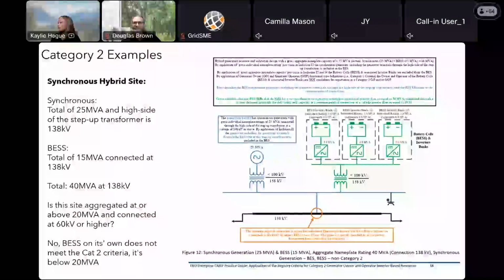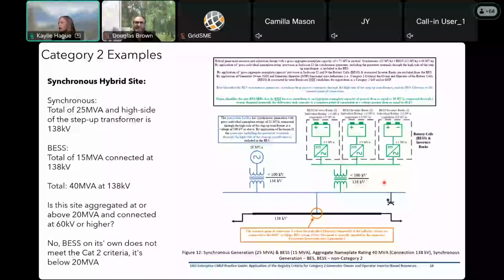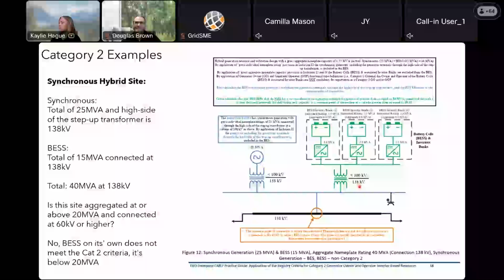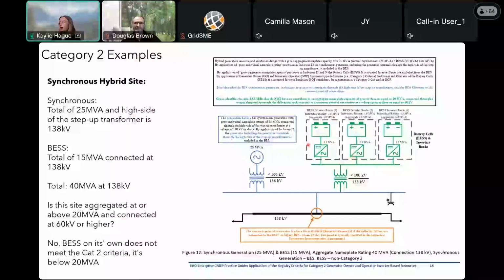All right, and last example here, another synchronous hybrid example. This time we've got a 25 MVA synchronous generation connected at 138 kV. This side does meet the BES synchronous generation threshold. And over here we've got 2, 4, 6 BESS inverter banks individually rated at 2.5 MVA for a total of 15 MVA, and are connected at 138 kV. These are going to aggregate together for a total of 40 MVA at 138 kV. But this does not have to be registered because your IBR threshold is below 20 MVA. So this does not have to be registered as a Category 2 GO-IBR.